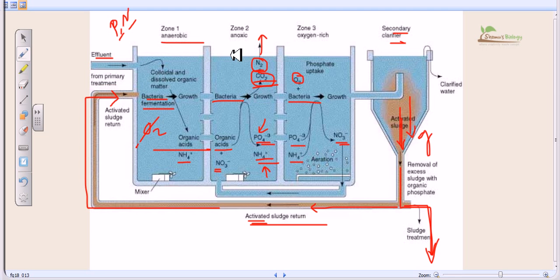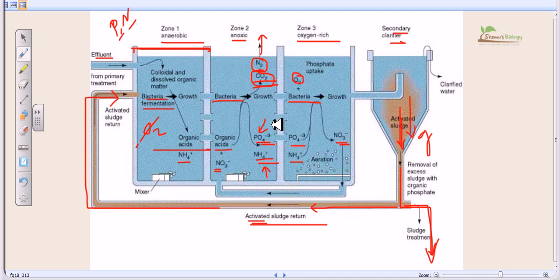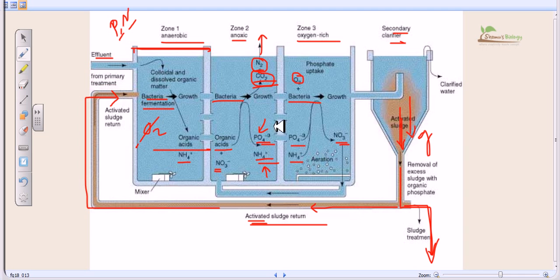There are three distinct zones in the secondary treatment: the anaerobic zone, the anoxic zone, and the oxygen-rich zone. The oxygen-rich zone uses aeration basins; the anoxic zone uses small basins without air supply but still open; and the anaerobic zone is totally covered with no air access. These three different groups of bacteria use three different types of nutrient sources and convert them into less toxic products. Chemical treatment then settles remaining nutrients like nitrates, and the cleaned water is sent to the downstream processor.